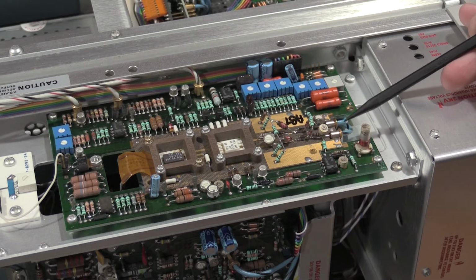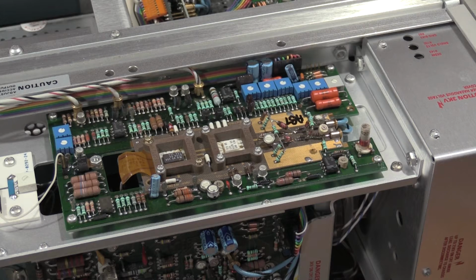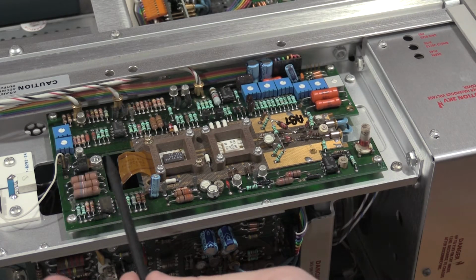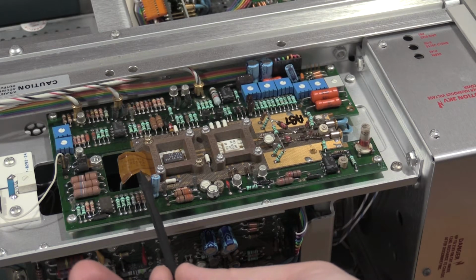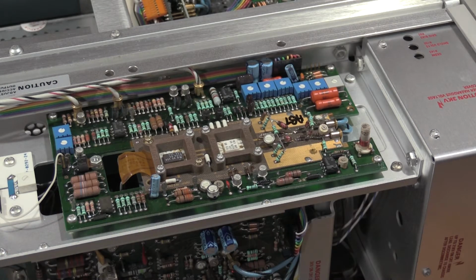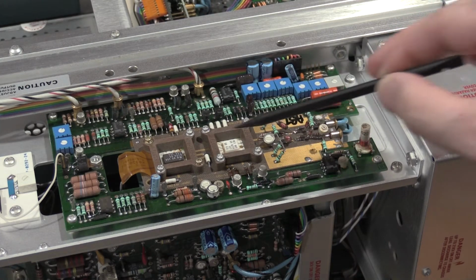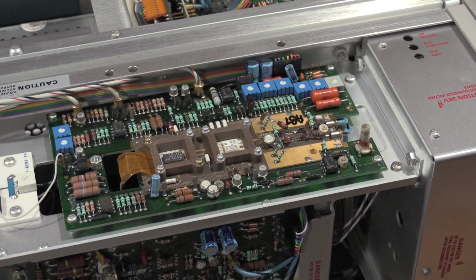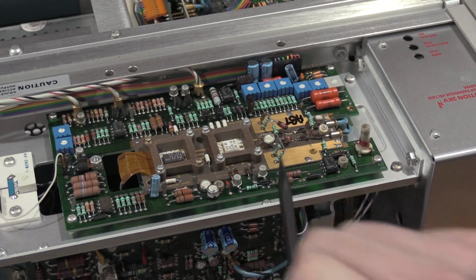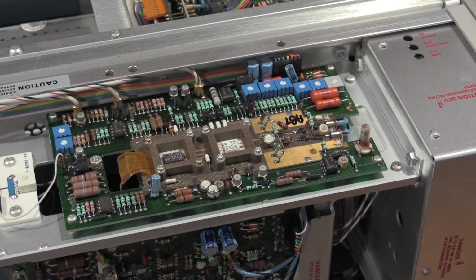We have the deflection plates coming in. This is the vertical, horizontals over here. So this is the high speed, and this is probably actually transmission line into the CRT, so we have a lot of high-speed, very fragile stuff in here. The service manual even calls out using a non-conductive tool, so none of this gets shorted out and these ICs get blown up. There's a lot of unobtainium in here. If I run into a problem, I will not be able to get any more of these hybrids. There's another one down here for the Z-axis over that way, which we'll get to. The horizontal doesn't have any of the super fast stuff. So I'm going to have to be very gentle while we're working in these areas to make sure nothing happens to these hybrids while we're calibrating.